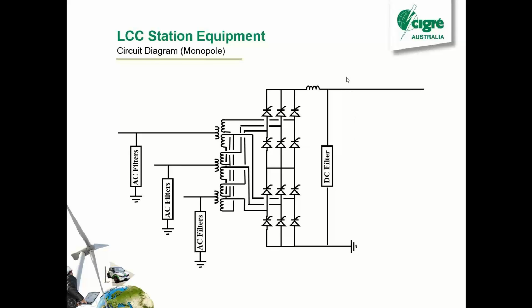And that's mainly because the transmission line acts like a big aerial, and if you've got too much harmonics on the DC side, you can end up with interference, especially if you're going near cities. But it's not so much of a problem these days with most communications going to fiber optics. But back when everything was copper, they used to have issues with harmonics on the DC side causing audible rings in telephones and stuff like that. With our characteristic harmonics, 600 hertz, you can hear that pretty well with the human ear.